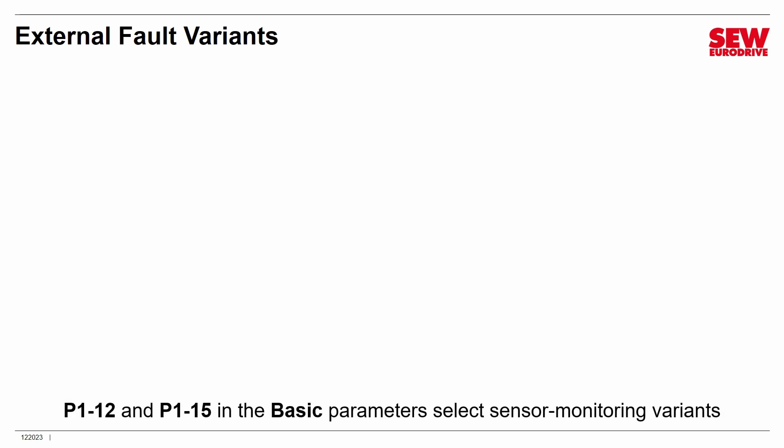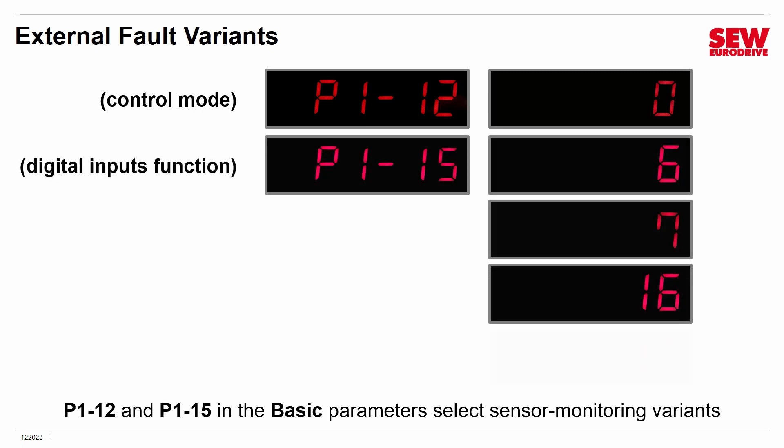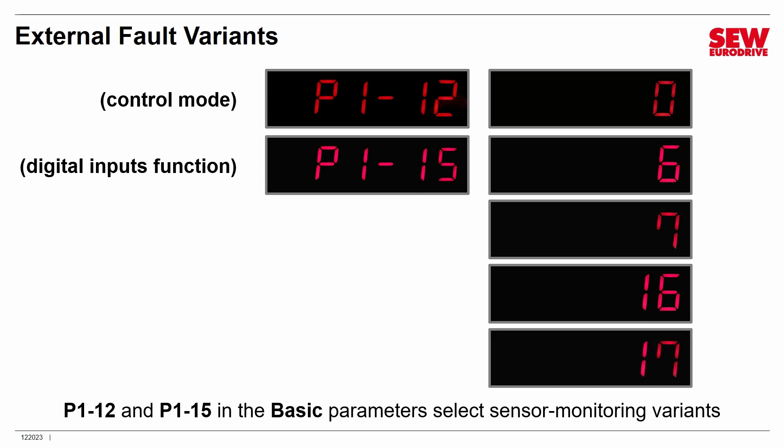Once your sensor is wired up, you need to switch to terminal control mode and pick a variant that monitors the sensor. Parameters 1-12 and 1-15 in the basic parameters are what you need. Set parameter 1-12 to 0 for terminal control mode, then set parameter 1-15 to one of the four possible variants: 6, 7, 16, or 17 — all of which can monitor external sensors.